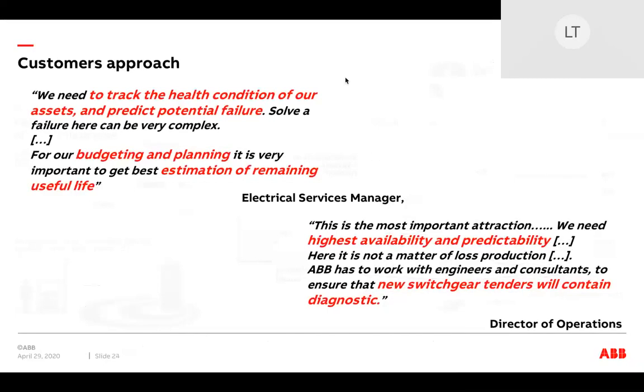Budget planning, very important. If you know what the failure points are and you understand the asset base, then instead of performing time-based maintenance and spending money where it's not needed, you can then improve the efficiency of your budgeting. And by doing that, the estimation of the remaining useful life is known to you. Also, other customers have asked us for highest visibility and predictability. On new switchgear tenders, they will contain diagnostics. We're seeing now that many customers are asking for switchgear that provides analytics so that they can start to understand the predictability of failure.